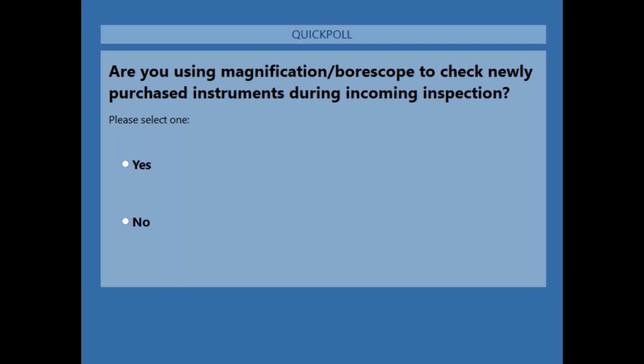So poll question number 2 is: are you using magnification or a borescope to check newly purchased instruments during incoming inspection? This was interesting because Children's Bellevue Clinic in Seattle said that when the staff examined instruments that should have been clean, they had tiny amounts of debris on them. As you know, when a surgeon uses a loupe in a well-lit operating room, those tiny things look like boulders, which you cannot really see with the naked eye. So it's important to know what you're sending up, and to at least look at it under some kind of magnification to see what the surgeon sees.